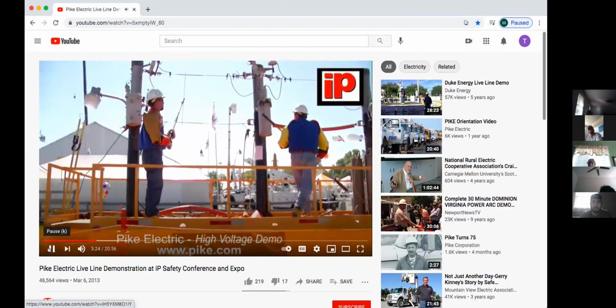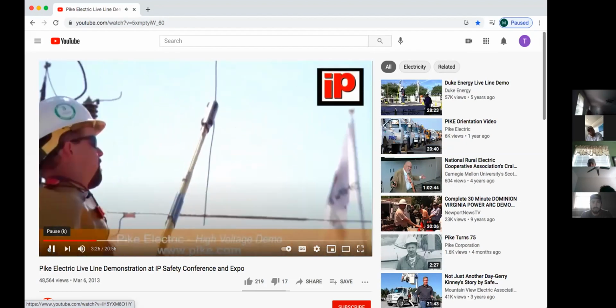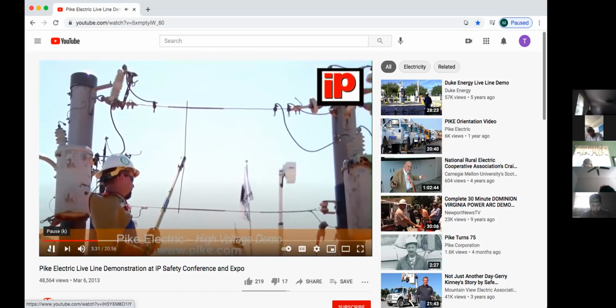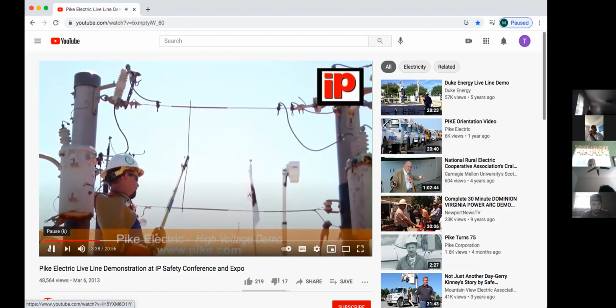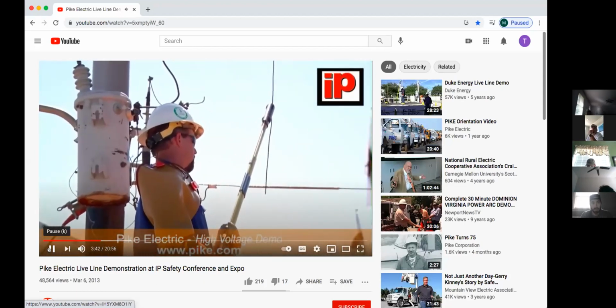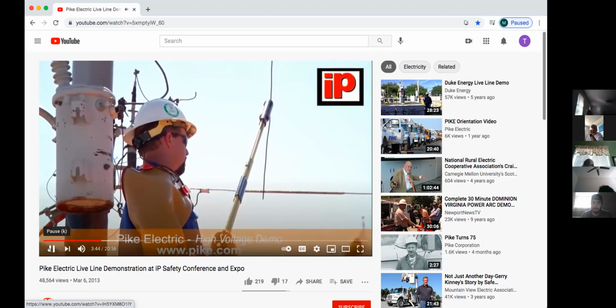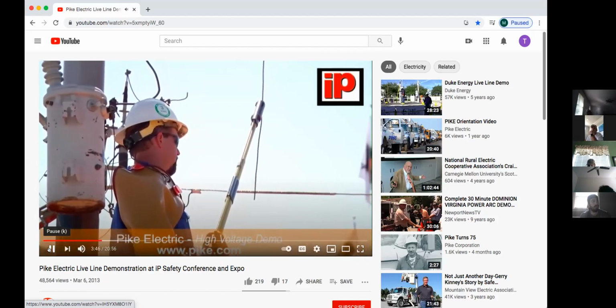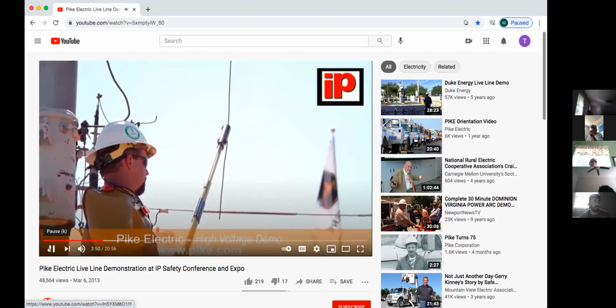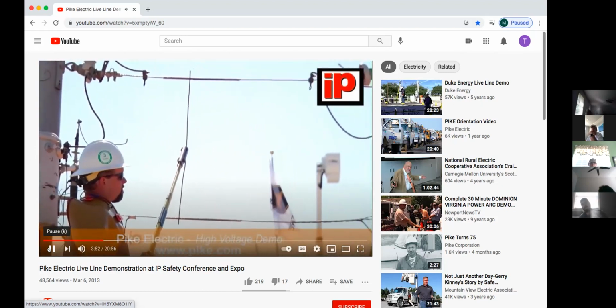The middle recloser, the middle pole here has a recloser on it. The recloser is designed to operate when there's a fault on the line. In normal operations, that recloser will operate 3 different times. And on the 4th time, if that fault hasn't been cleared, it will stay out. We're going to put the recloser through a fault situation. If you listen real closely, you can actually hear the recloser clicking and counting each fault, each time that fault hits the line. You ready?